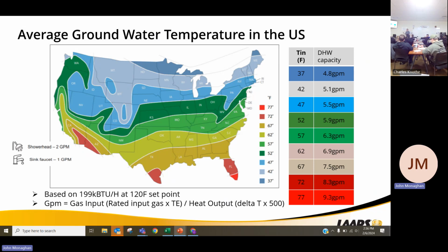So as we're looking at sizing these, our output is going to be based upon our groundwater temperatures. Sometimes the big myth is, we have really low groundwater temperatures, our GPMs are going to plummet. With higher groundwater temperatures, we're going to get more performance out of it. You live down there in that wonderful world of Florida, you can get almost 10 gallons a minute out of this tank. Let's say very warm water.